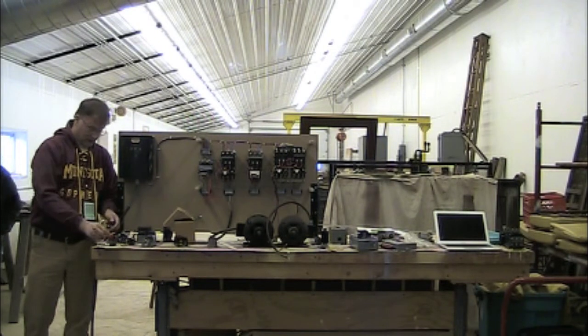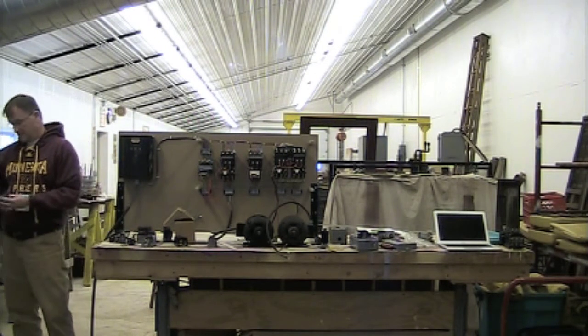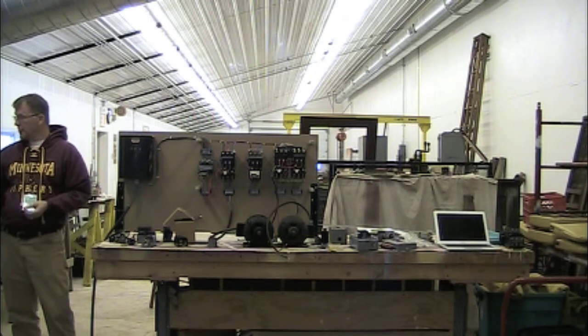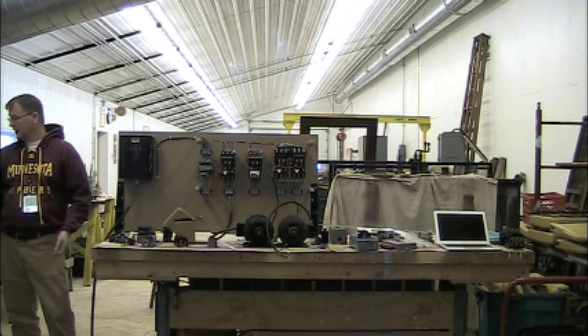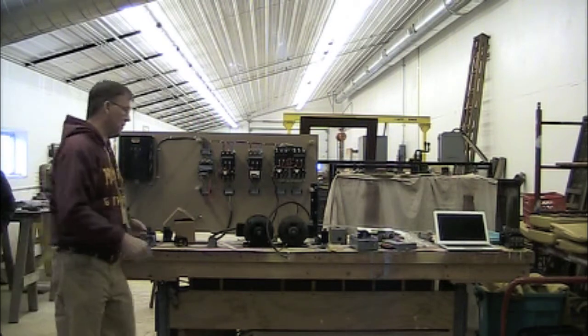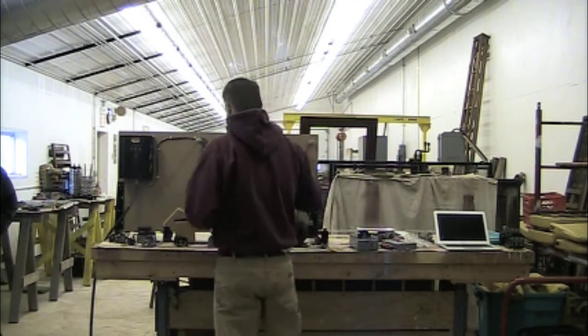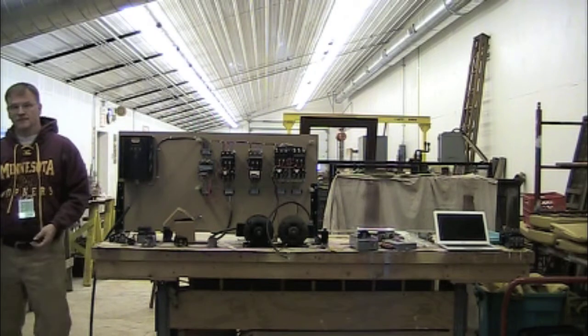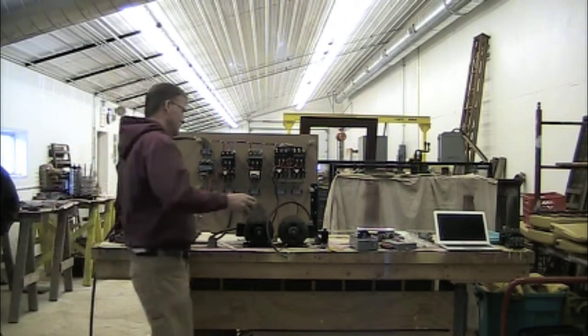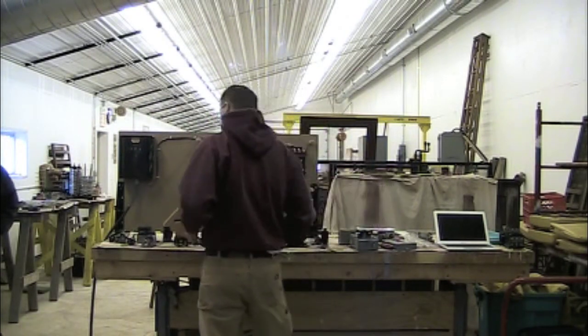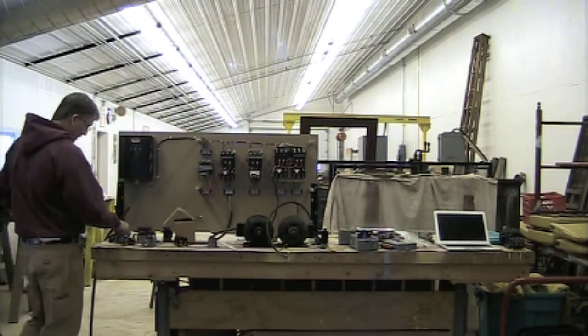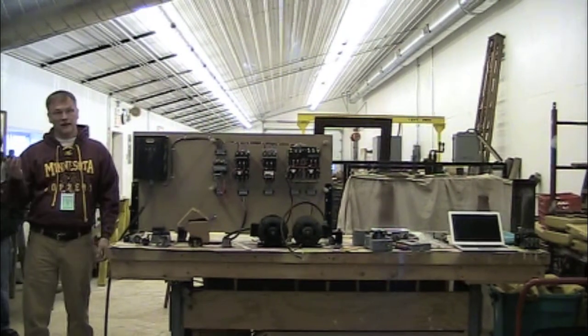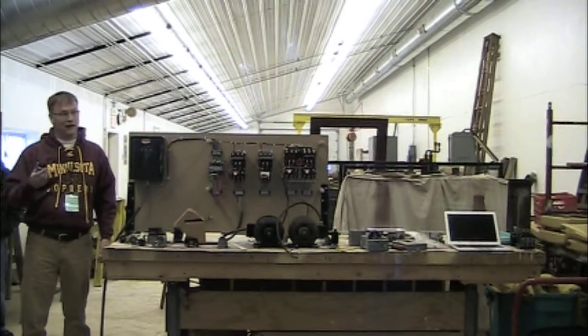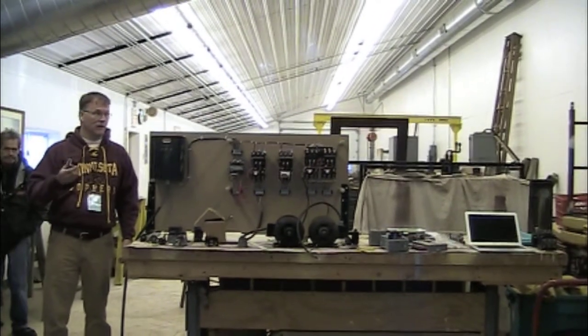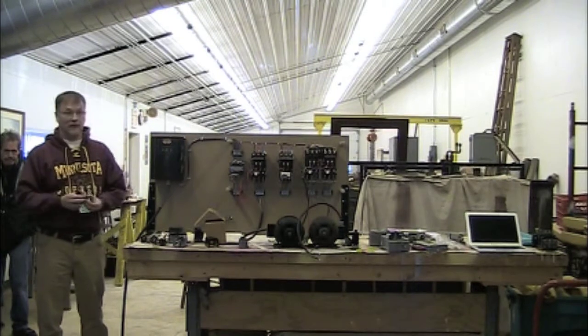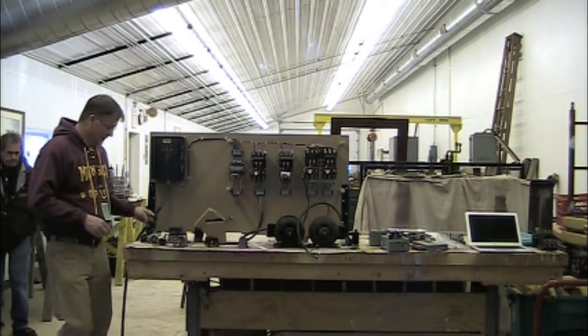So I'll just pass a couple of these around. There's 30 millimeters as the size of the mounting hole. Yeah, that's the size of the mounting hole. So those go in these standard little operator boxes. In the same line, you can get a pilot light. Pilot lights are specific. This one's 120 volt. You can get them in 24 volt or whatever. Some have little transformers built into them.